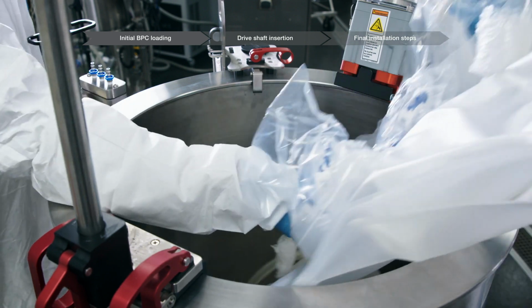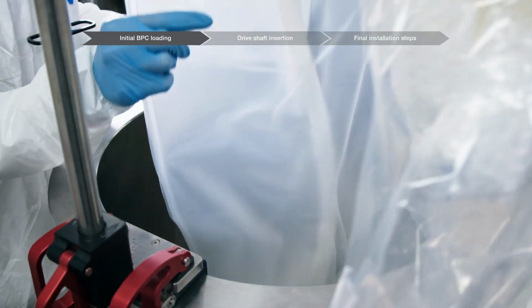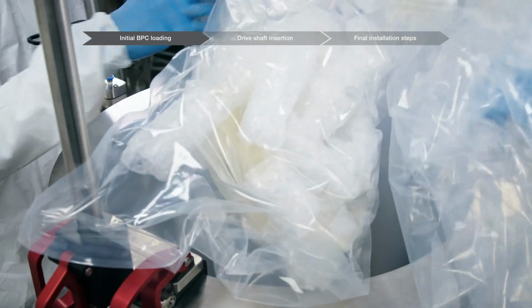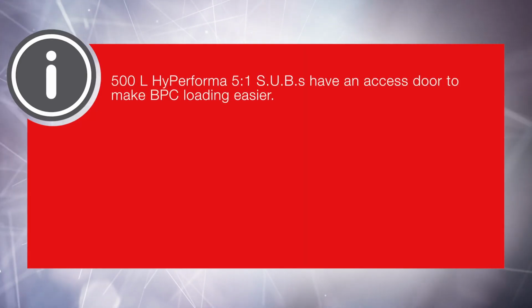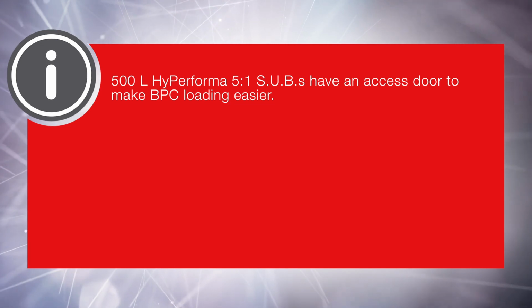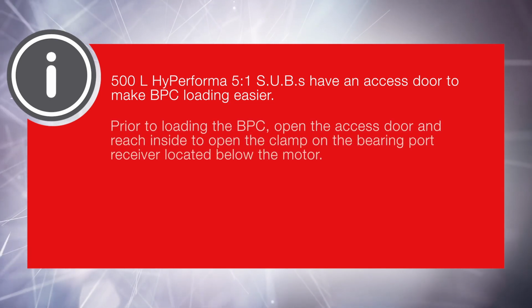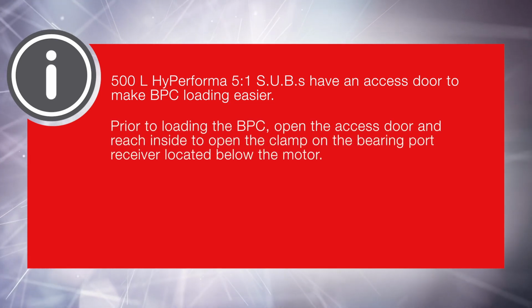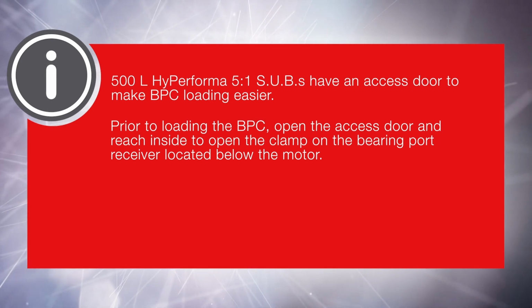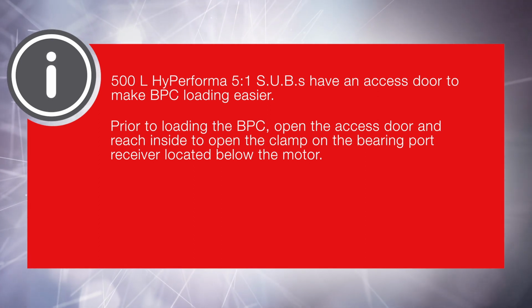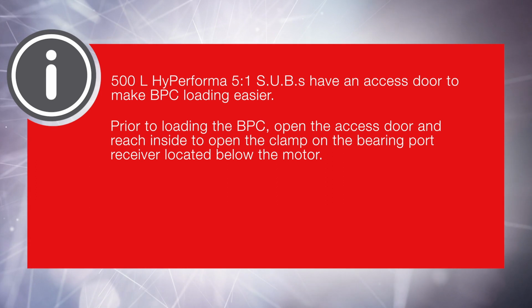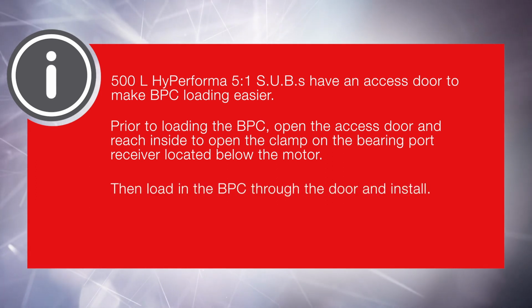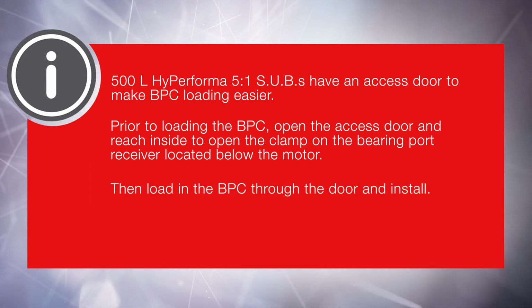Load the BPC from the top into the outer support container, avoiding any sharp edges that may damage the BPC. 500-liter HyPerforma 5:1 S.U.B.s have an access door to make BPC loading easier. Prior to loading the BPC, open the access door and reach inside to open the clamp on the bearing port receiver located below the motor. Then load in the BPC through the door and install.